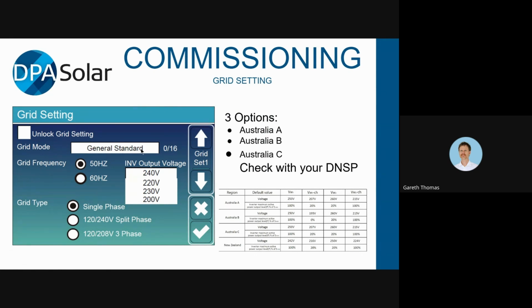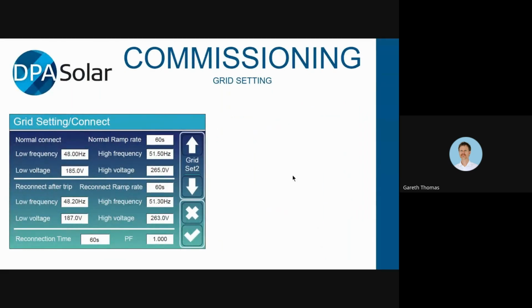So in grid settings, you have the grid mode settings here, and you're basically going to be selecting between Australia A, Australia B, and Australia C. You'll need to check with your DNSP which one of them applies to you. But most of you probably will know that from installing other inverters. I think we're Australia A here, aren't we, David? I'm not sure. Yeah, that's what the one in the office had said to me. Once you've done that, it's going to pre-fill all of these pages. So I'm just going to go through these pages pretty quickly, but you shouldn't really need to edit these. You could, perhaps if you're off-grid, you might change some of these, like the reconnection time, but I'd suggest that you leave them all as standard most of the time.